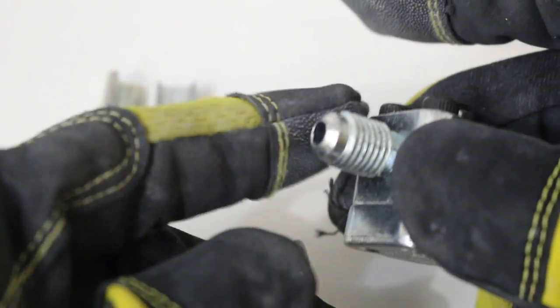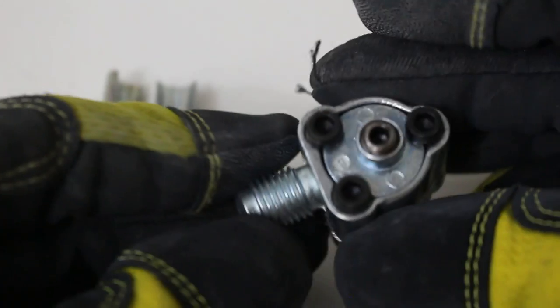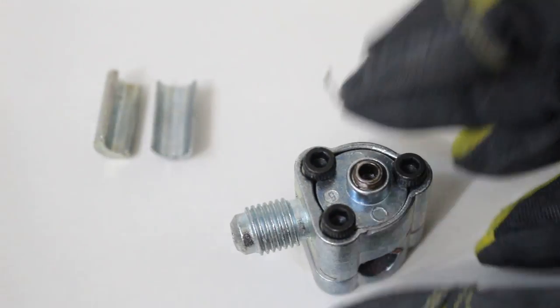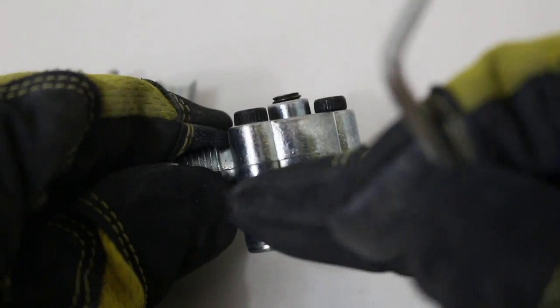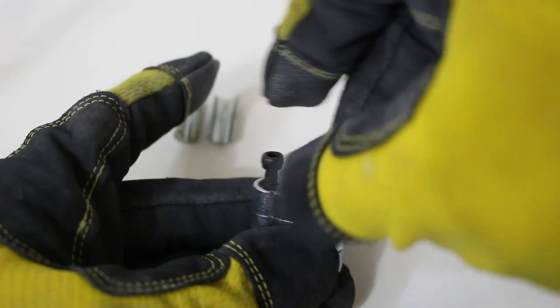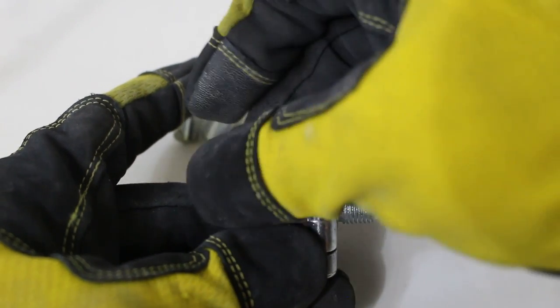Let's get straight into it. So right here is our access port, and here's our cap with the gasket inside. There is no pin on this valve, so it's important to know how this works. 1, 2, and 3 are the screws that we're going to take apart, so we can separate this valve in half. As you can see, we have a mark here. So, let's begin by unscrewing this. Once we take off these screws, we're going to be able to separate the top of the valve and the bottom.